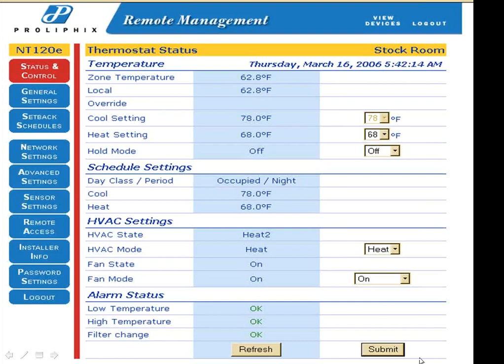You actually get 3 different unique day profiles to work with: occupied, unoccupied, and other, blue, yellow, and pink respectively. Each one of them has 4 times throughout that day, like a normal thermostat would have. So under occupied, I have it starting at 7 o'clock in the morning. It does 71 degrees on the heating set point, 75 on cooling, and then it changes throughout the day. Once I set those up the way I want, I go down to the weekly schedule and I flag those to match up with what I want to do.